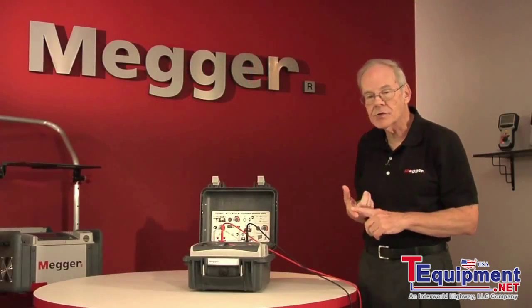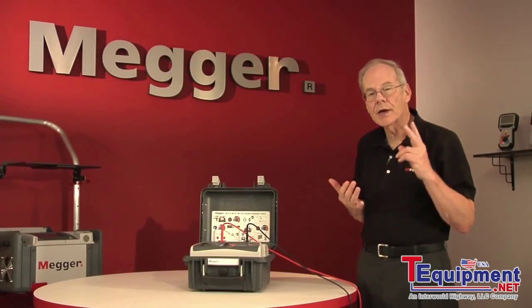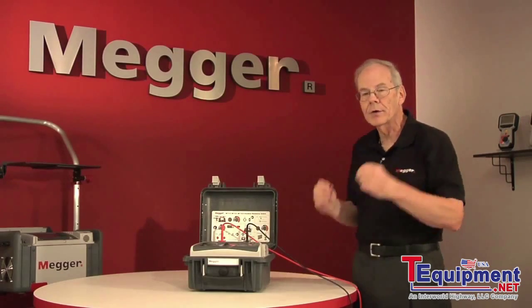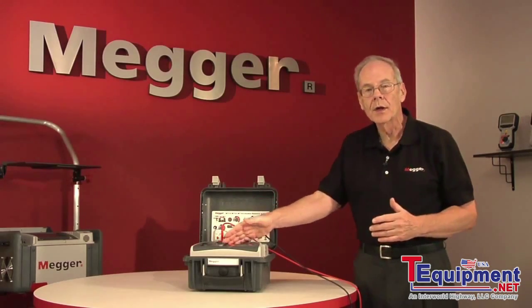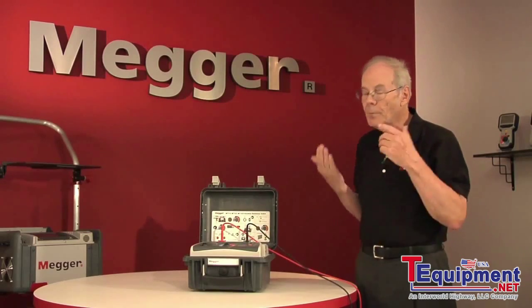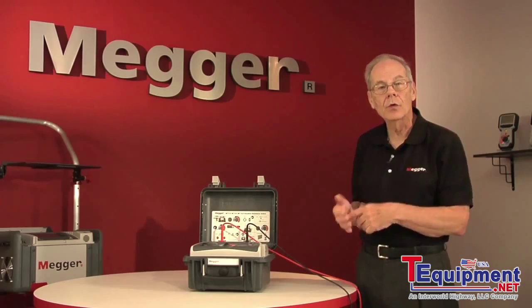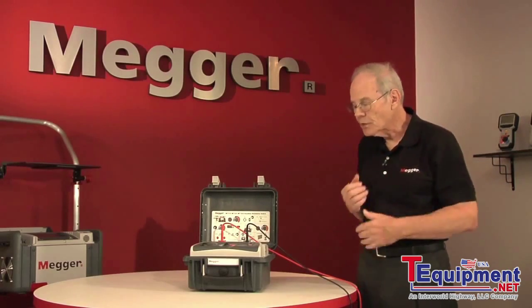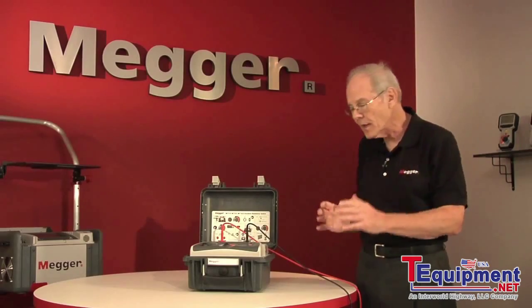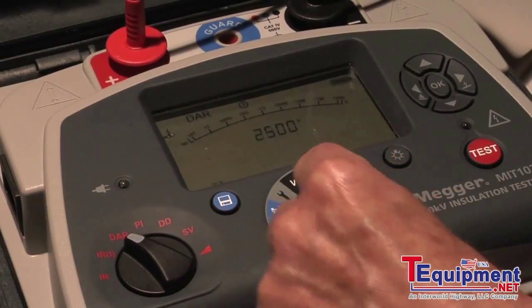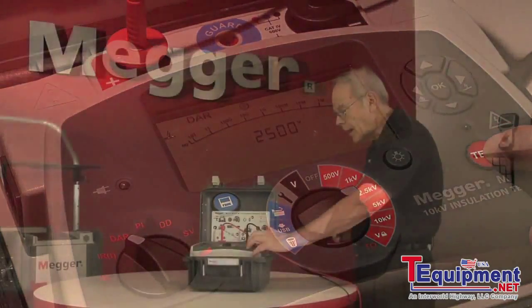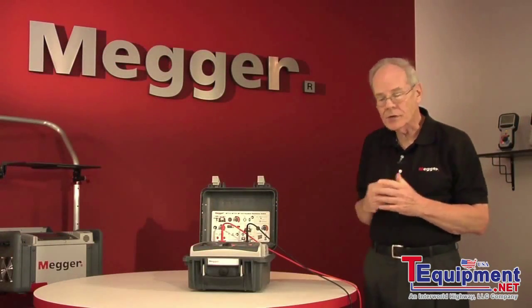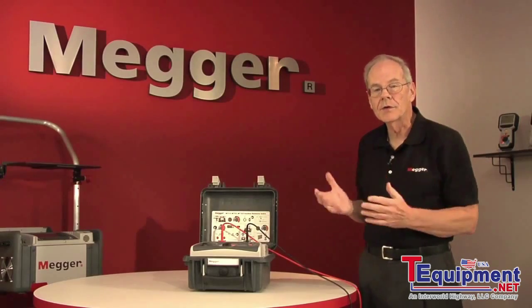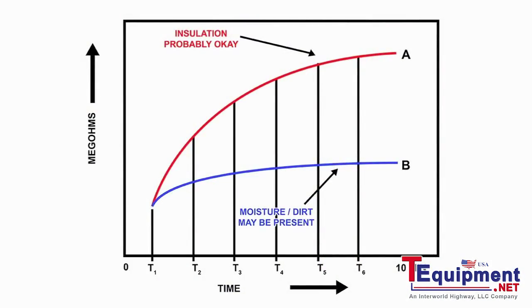In this case, the tester will record values at two select times, which the operator sets up and designates on the setup menu. Typical values are 1 minute into 3 minutes or 30 seconds into 1 minute. The tester will automatically then run the test for that time. So we'll select that and we'll get it underway. And then at the end of the test, all the data is shown on the display. So it will show you time 1, it will show you time 2, and it will do the calculation for you in terms of the ratio.